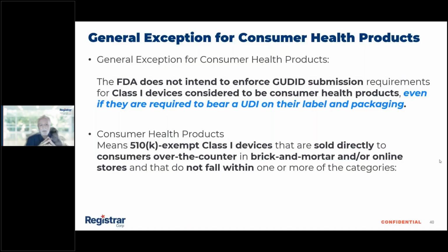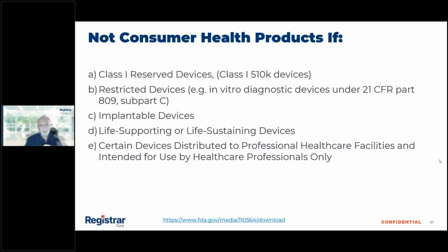Consumer health products are sold directly to consumers over the counter in brick and mortar or online stores, and do not fall within one or more of the following categories. When we talked about Class 1 already: if you have a 510(k) Class 1, then you need to feed the GUDID database. There are also restricted devices, for example in vitro diagnostic devices, then Class 1 implantable devices, and Class 1 life-supporting or life-sustaining devices. There are not that many in the database, but if your device falls under that, then it's definitely not a consumer health product, and you have to submit your UDI data, including the product information, to the GUDID.